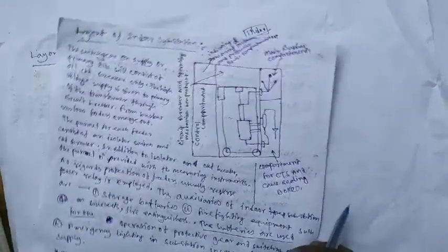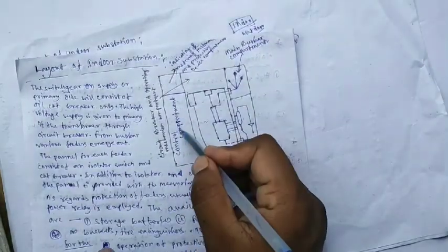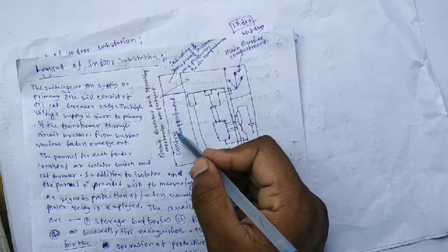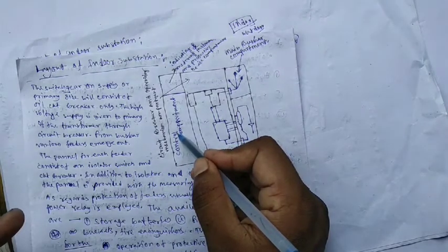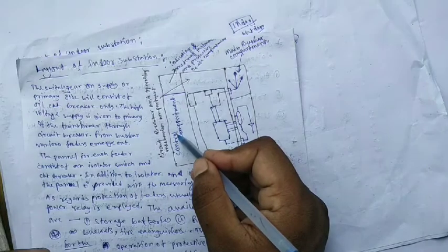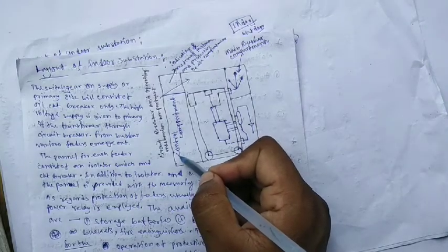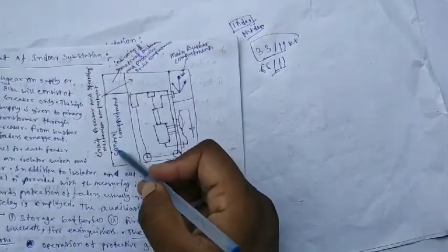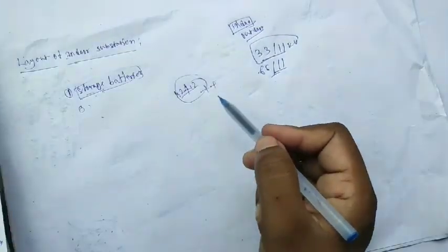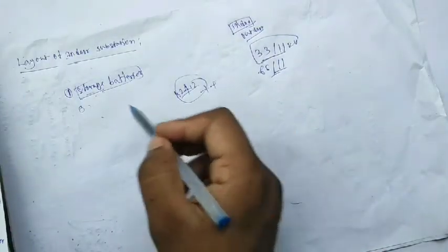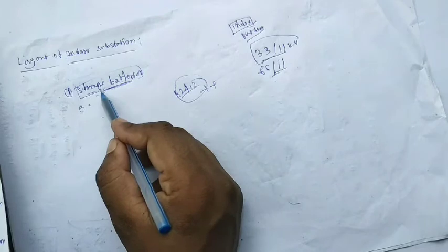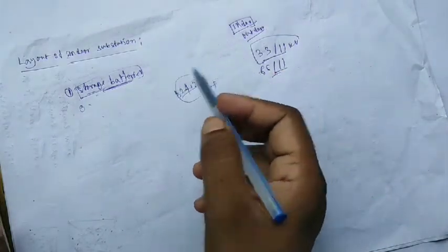Substation instruments means the control compartment is used here too. The control compartment cannot produce electricity by itself, so an electric supply is needed for the control circuit to operate. The storage battery feeds power to this control circuit and other equipment used in the substation, different types of instruments for controlling and measuring.